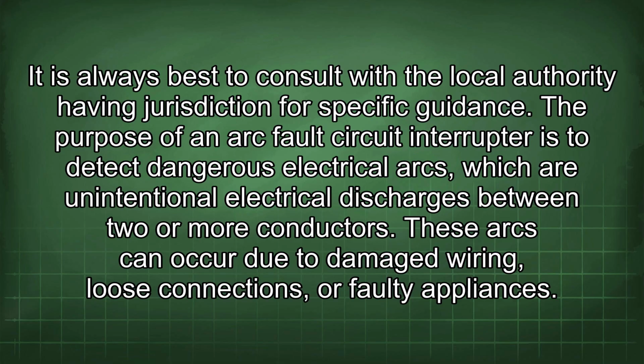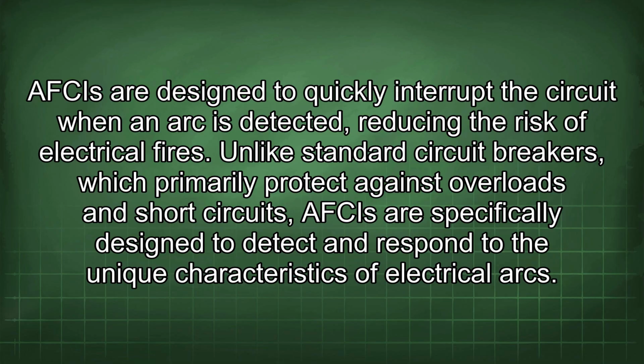The purpose of an arc fault circuit interrupter is to detect dangerous electrical arcs, which are unintentional electrical discharges between two or more conductors. These arcs can occur due to damaged wiring, loose connections, or faulty appliances. AFCIs are designed to quickly interrupt the circuit when an arc is detected, reducing the risk of electrical fires. Unlike standard circuit breakers, which primarily protect against overloads and short circuits, AFCIs are specifically designed to detect and respond to the unique characteristics of electrical arcs.